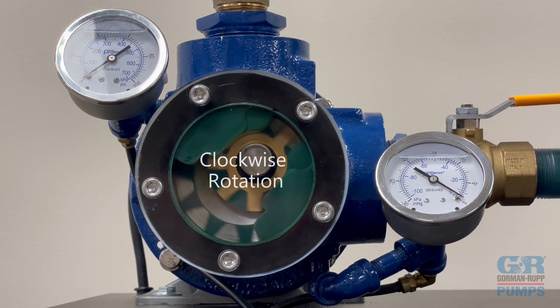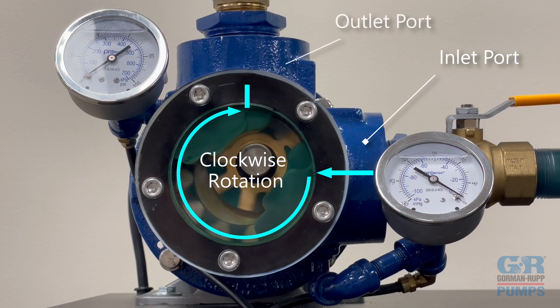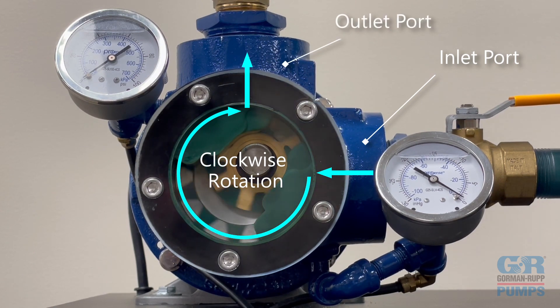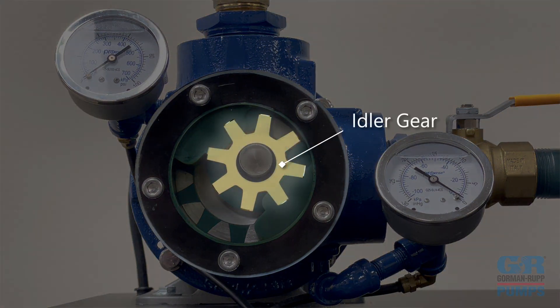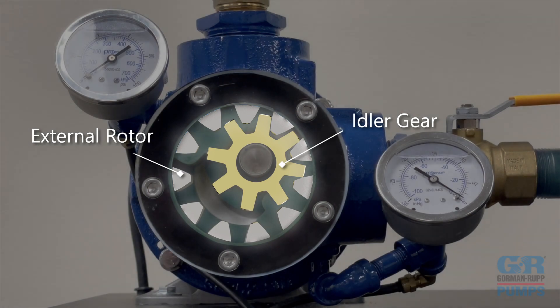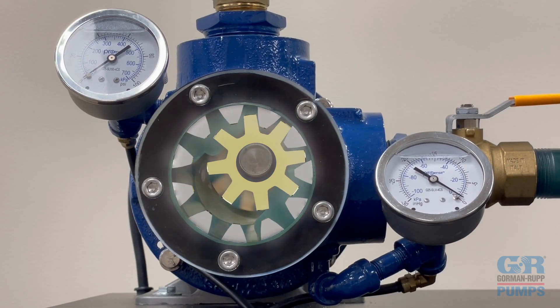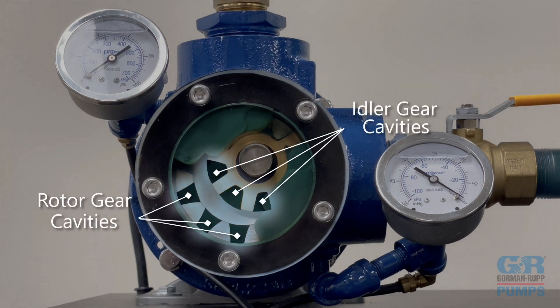As the pump operates in a clockwise rotation, the liquid enters the right-hand inlet port between the exterior drive gear or rotor and the smaller driven interior gear or idler gear. The gear-within-a-gear principle consists of an internal idler gear driven by an external rotor. A definite volume of liquid is captured in the cavities between each rotor and idler gear tooth as the teeth come out of mesh.